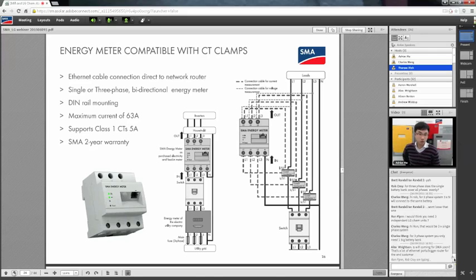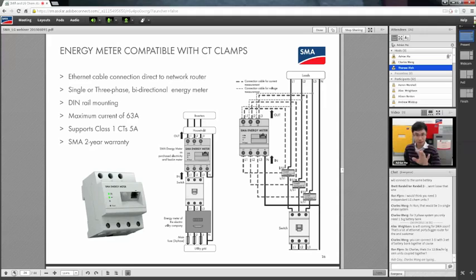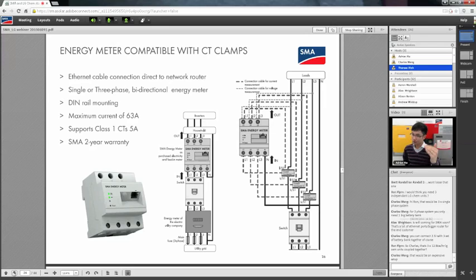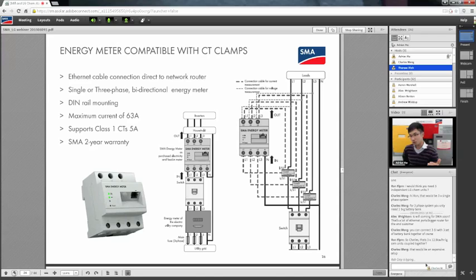For commercial sites larger than 63 amps, use the CT, class 1 CTs with 5 amps maximum. Beware, only 2 years warranty on this one. A lot of installers have trouble installing this thing - make sure all the loads are installed on the load side of the meter. In other words, put the meter as close to the fuse or main switch as possible. If the wiring isn't done properly, the system won't measure the proper parameters.